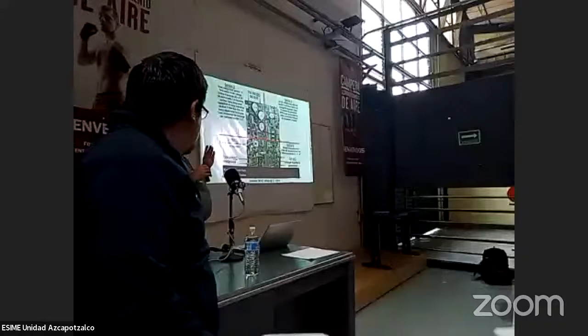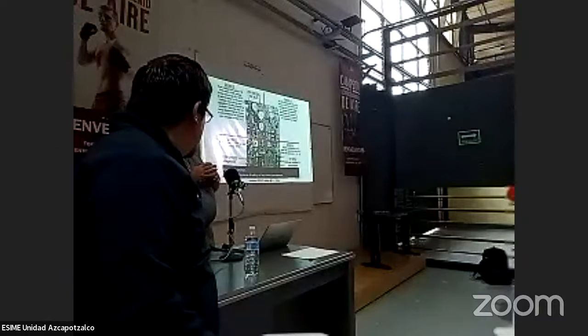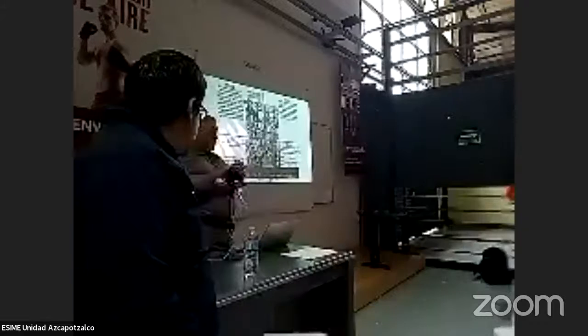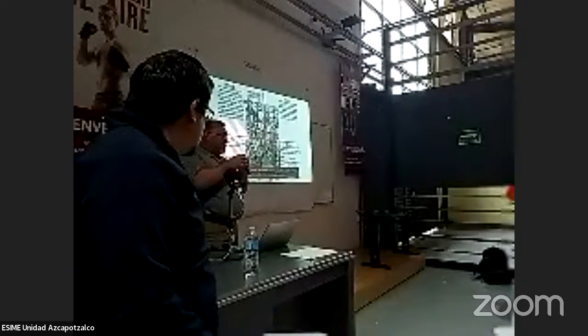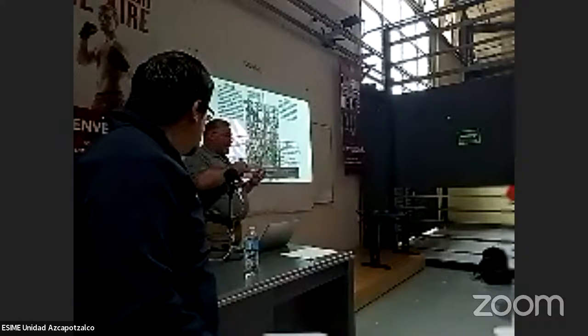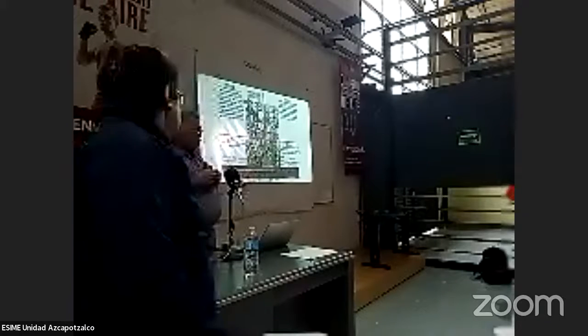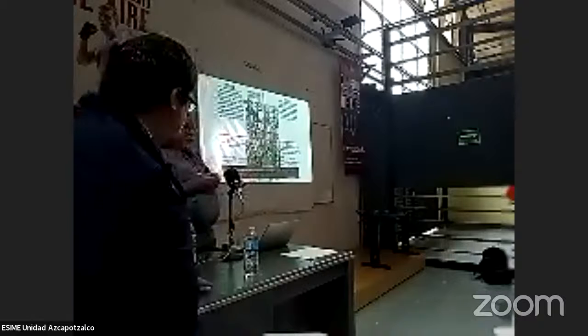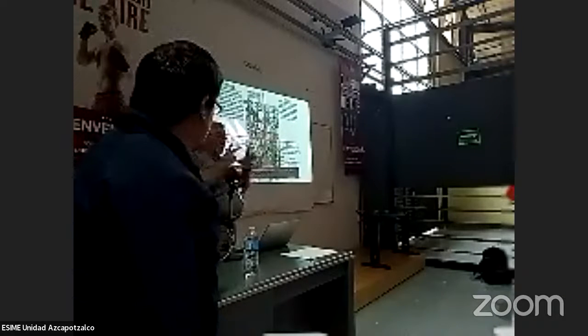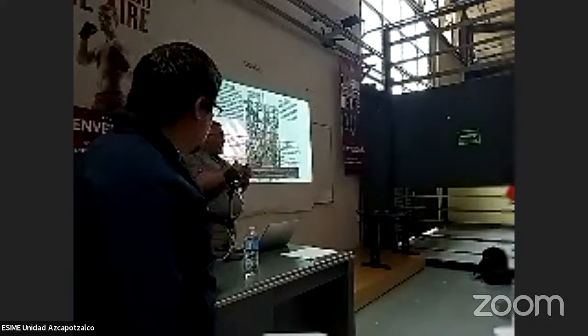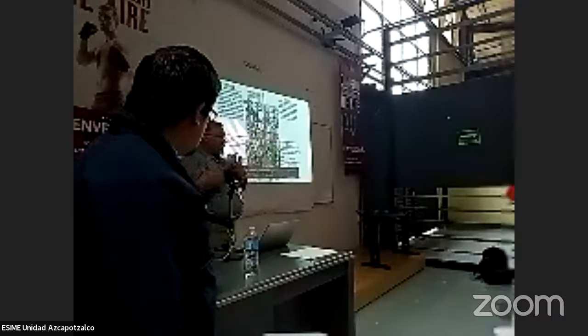If the board is sending voltage, that's the board. Sometimes the compressor can be locked up, and the board is sending voltage to the compressor. But if the compressor is liquid locked, there is a procedure you can do to try to get that to go away. One of the things you can do is pull some refrigerant out and see if you can get it to start. Another thing you can do is put a belly band crankcase heater on the compressor. If you start to see ice up and start to see that refrigerant boiling out of the oil, then most likely it was locked up. Once that dissipates, it can start again.